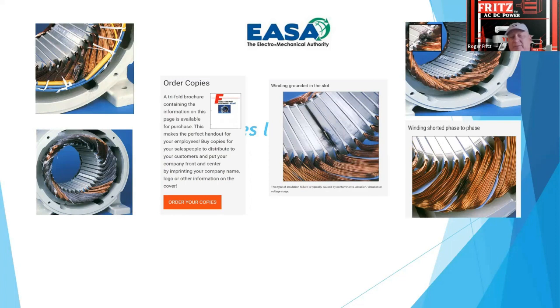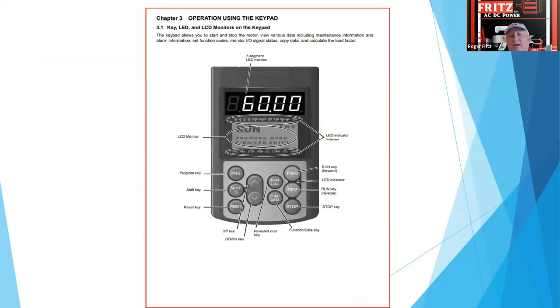And the book's very good. I mean, the little pamphlet, this shows where it shorted in the slot. A lot of times that's from mechanical rub, where the stator and the rotor, or the bearings may have gone out, started dragging, so it burnt the insulation, because the windings need to stay isolated from the steel. This shows a phase-to-phase spike that happened. So being motor people, we like to look at what's really happening in the motors, not just slap something on and say it's all going to work.